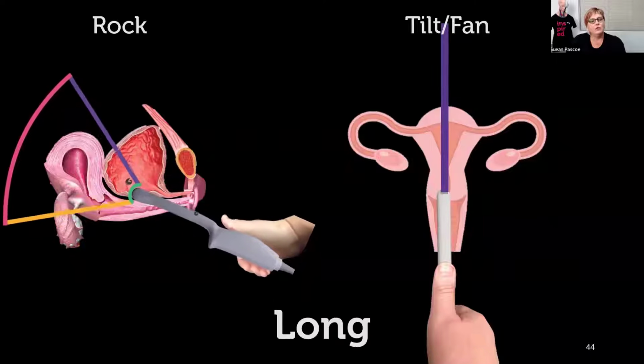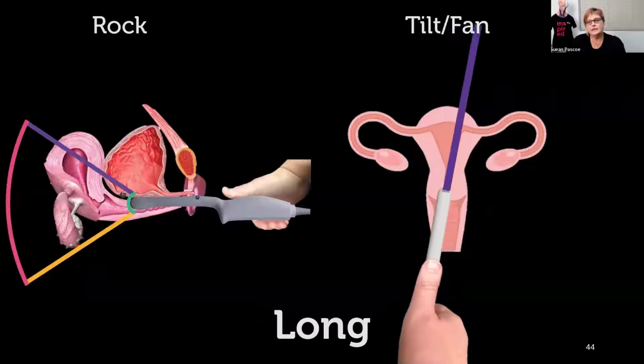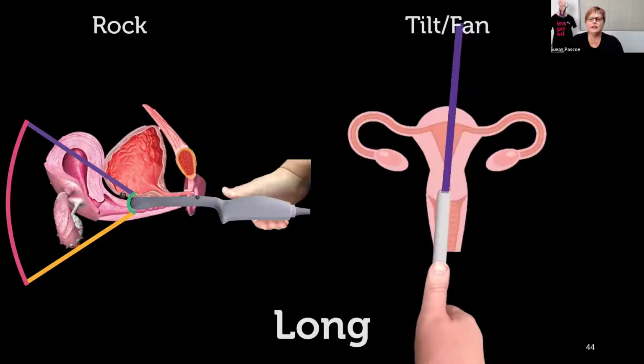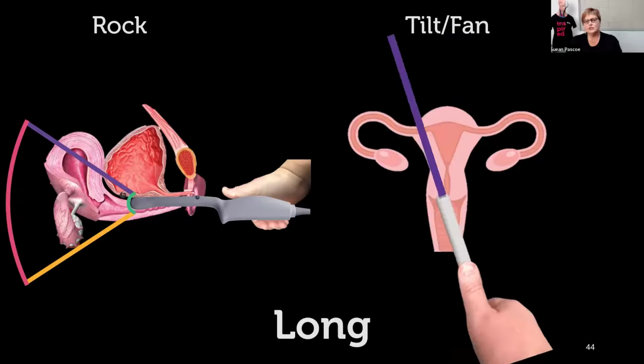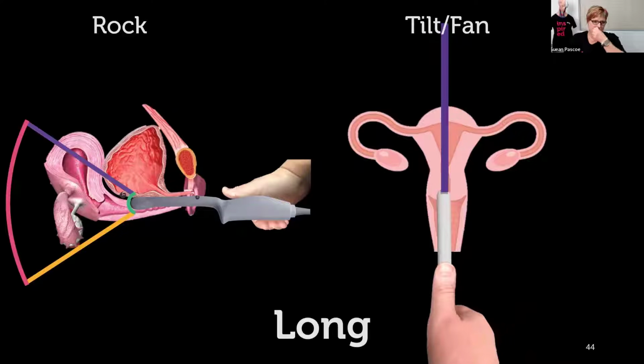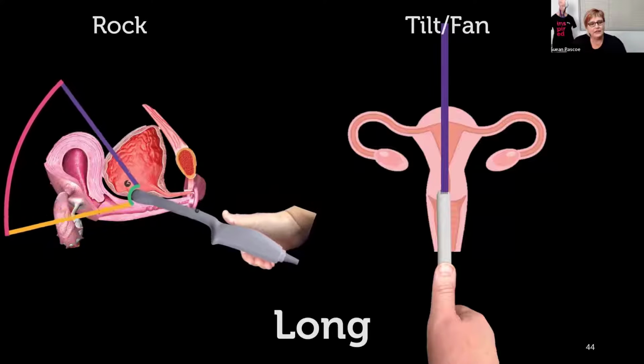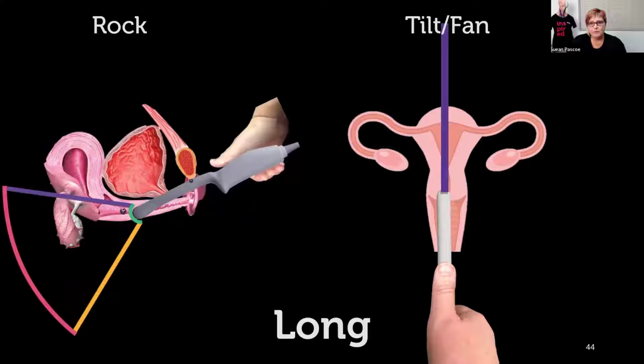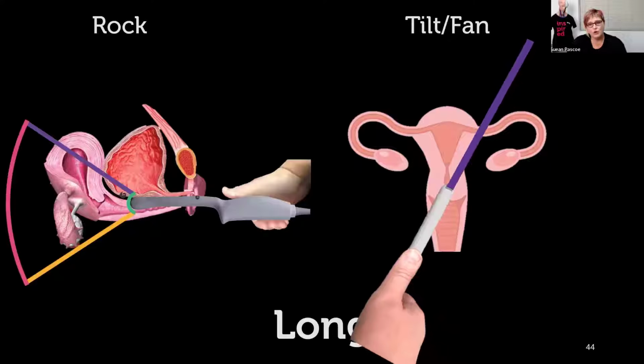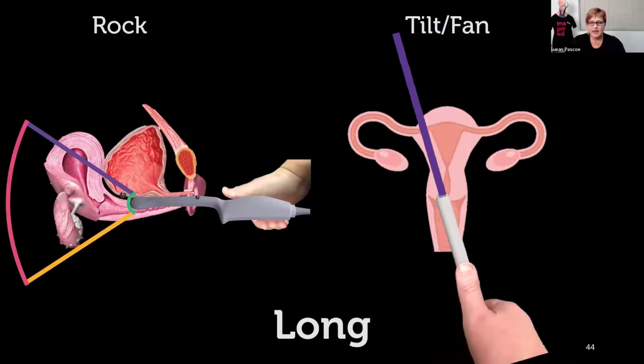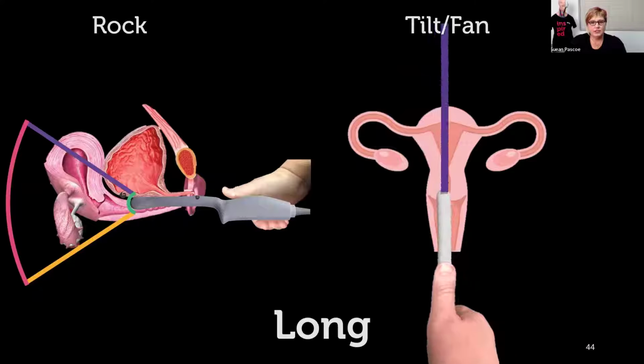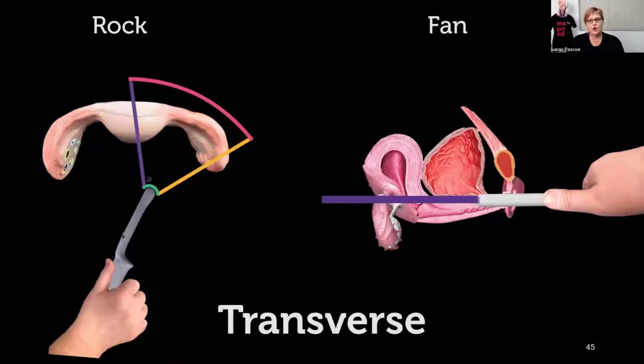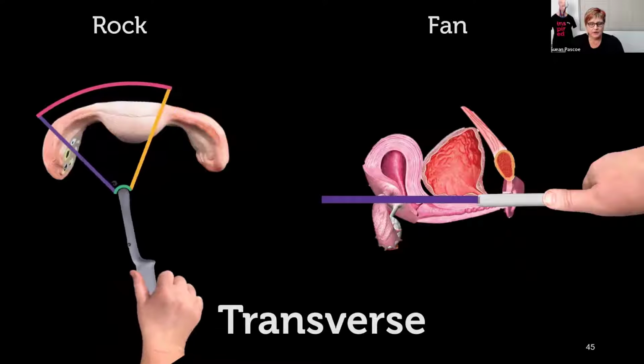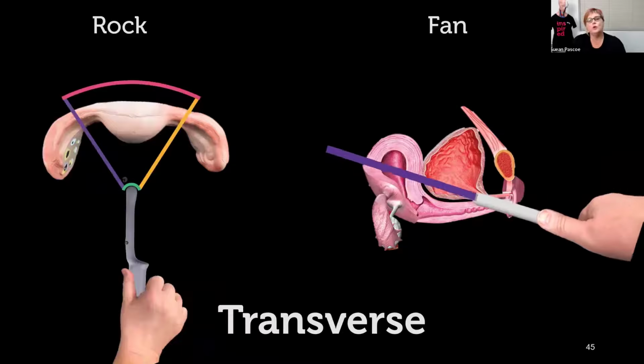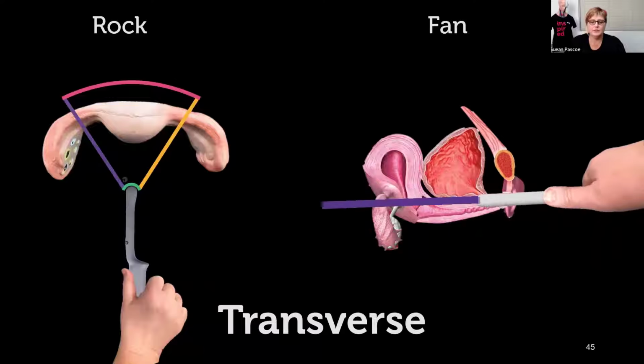And so we are rocking up and down. And essentially, fanning, I should say, we're fanning up and down, and essentially we are going from one side to the other side to create a three-dimensional view. So you can see in this animation, the rocking motion is along the length of the probe. The fanning motion is across the short face of the probe and creating the scan. And when we compare that on a transverse image, we rock to position organs in the middle of the field of view. And again, the fan motion will create the slices and allow that three-dimensional scan.